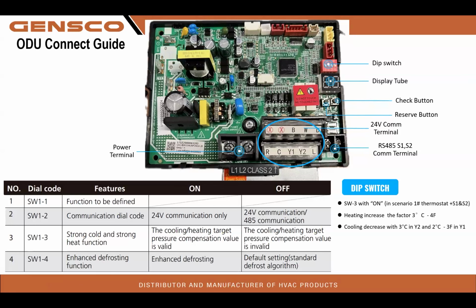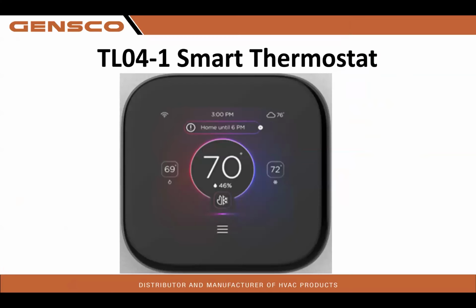Now, I will say in full communication mode, you will not have to, right out of the box, do anything with any dip switches. SW1-4, enhanced defrosting, for those freezing fog locations, Eastern Washington, Eastern Oregon, Idaho, Montana. It is highly recommended that you switch SW1-4 to the on position for enhanced defrost.